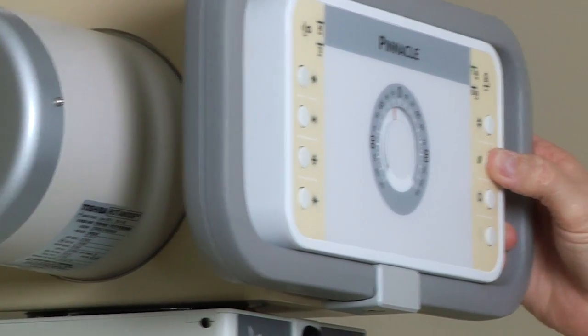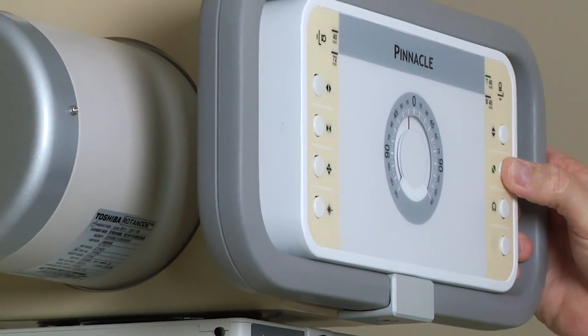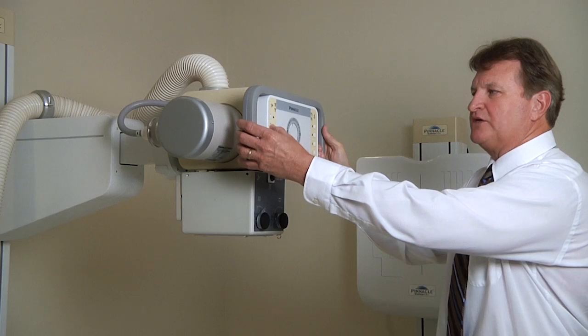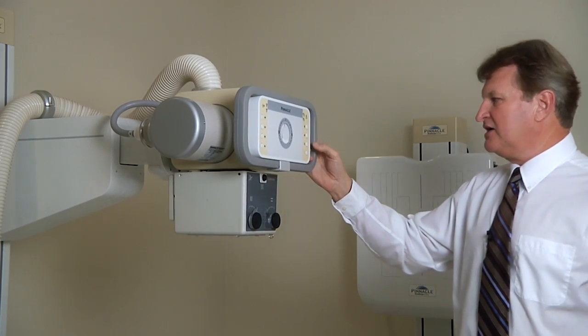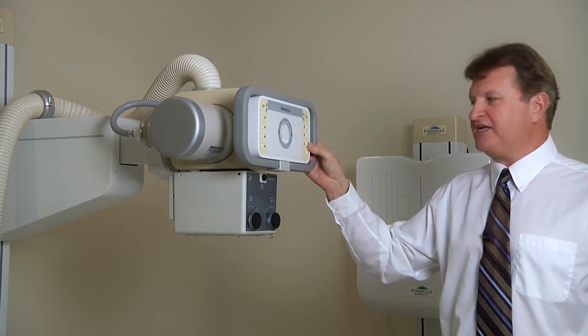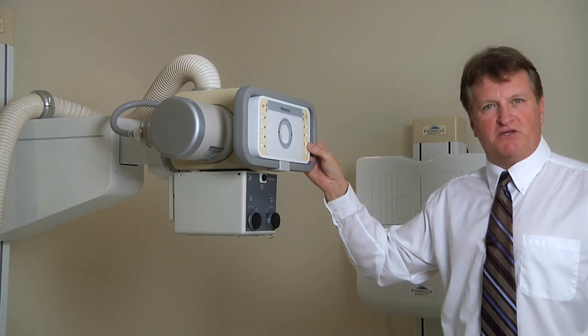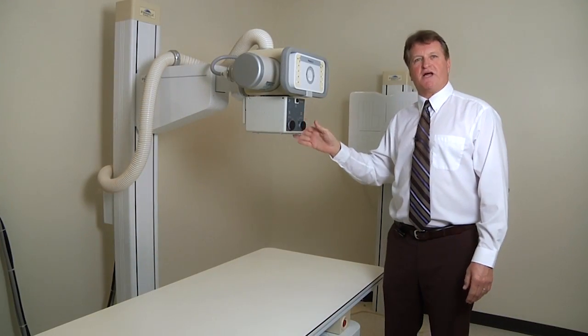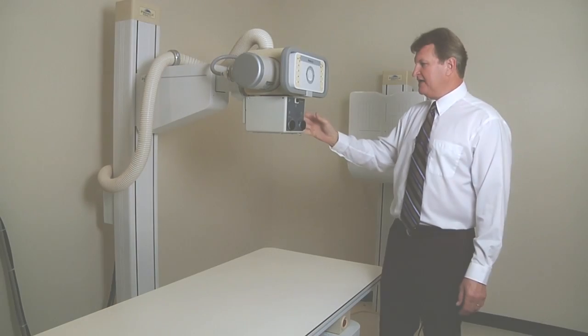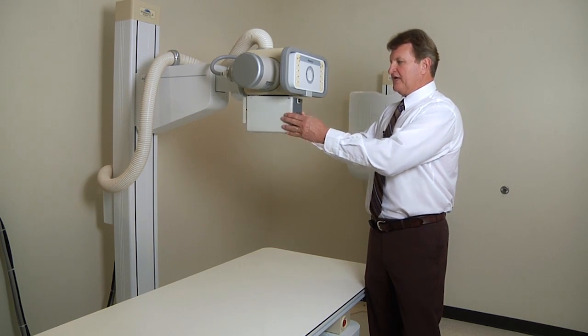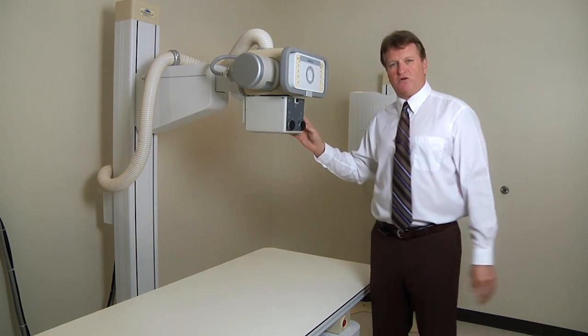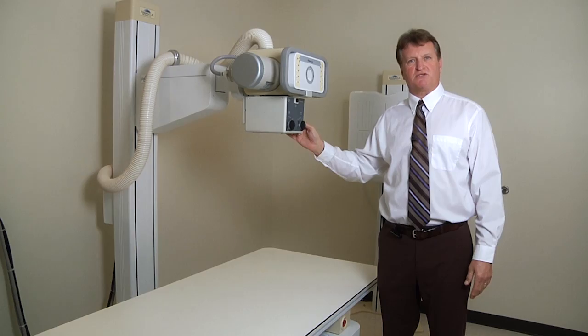Transverse movement is controlled by free flow with the right switch. The left switch is an electronic detent. Rotation includes a 15, 30, 45 degree manual detent. A laser centering light comes on when the cassette tray is pulled out and goes off when it's pushed back in. This particular collimator has rotation and is a manual collimator. An automatic collimator is also available.